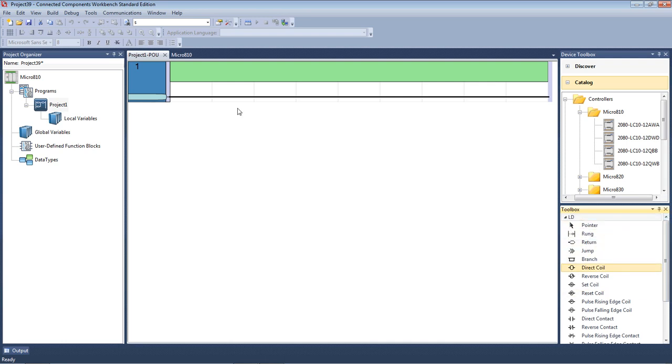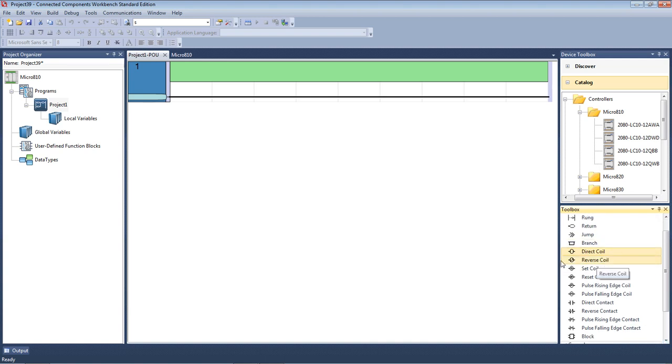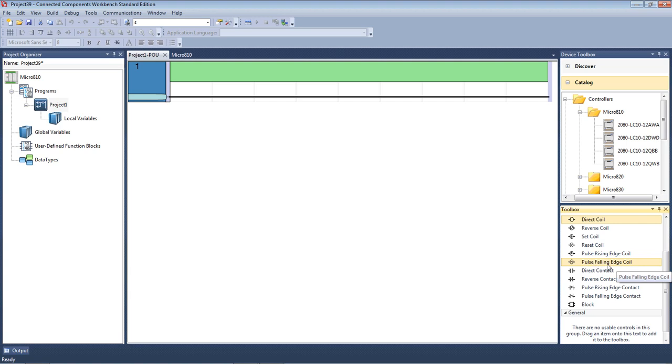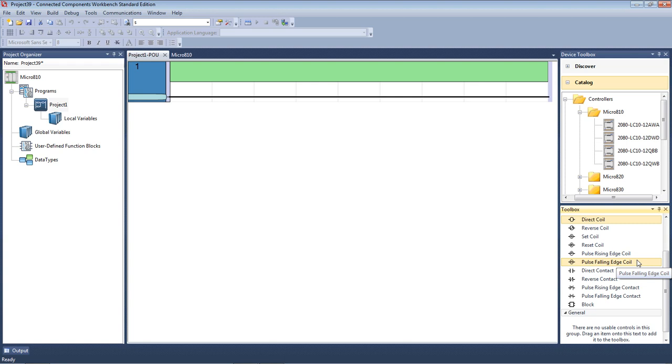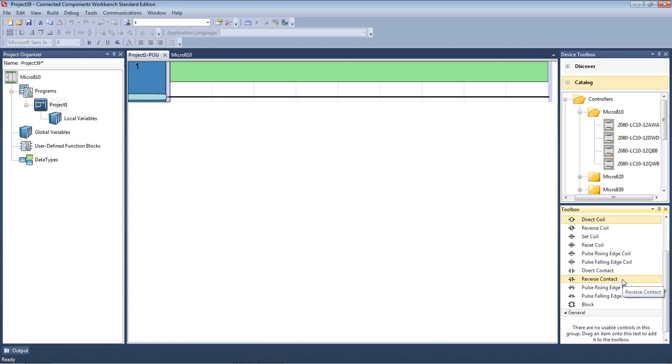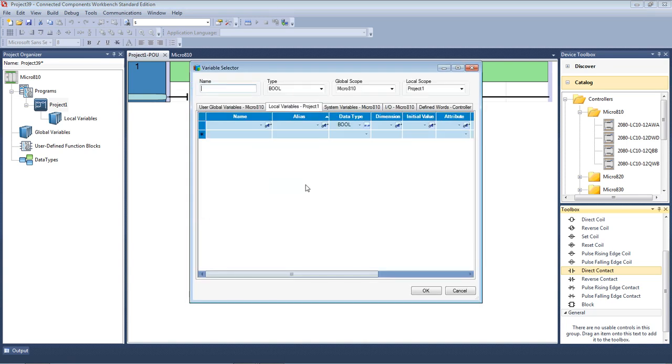Now, I've got a rung for when I can include an extra rung, I can drag that over. I've got return and jump, which are a couple of advanced programming functions, which we won't be using today. There's things like a branch, a parallel branch, what we call is just an output, is a direct coil. The inverse of that, the reverse coil. A couple of special functions, set coil, used in conjunction with a reset coil, you can set and reset. It's got some, what they call pulse rising edge, pulse falling edge, both coil and contacts. They're special features where they look for the rising edge of the input and the falling edge of the input. What we see as a normally open contact is here is a direct contact, and a normally closed contact is a reverse contact. We'll be looking at a timer and a counter also today, and we'll use the block for that. So what I'll do now is I'll just drag a, I'll left mouse click on the direct contact, drag it over and drop it into my first rung of my program.